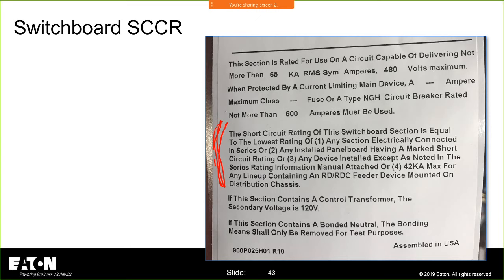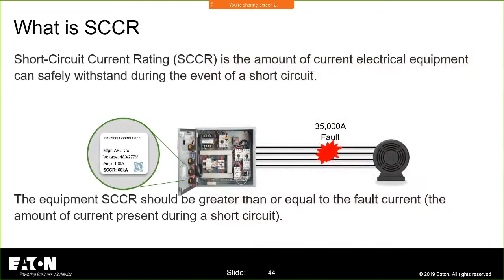So we don't really give you the SCCR, but what we give you is a recipe on how to calculate the short circuit current rating of that equipment. So it begs the question of whether we should have what your intention is field labeled on that equipment when you install it. I don't know if that's needed or not. I think you might see a public input next cycle, and that will be good fodder for discussion, because I don't think a lot of people realize that you're going to change the short circuit current rating of that equipment when you install these devices.